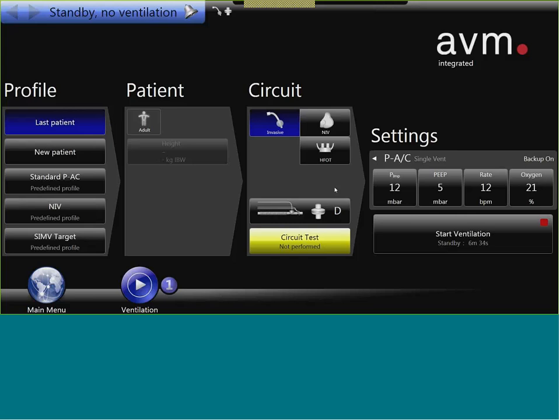So we did this on purpose. Usually you have to extubate a patient, then the patient is not ventilated at least for some seconds, and then you have to put on the mask of the patient again. And this, even when you're fast, can't be done in less than 10, 15 seconds. So there is enough time to switch the ventilator from invasive to non-invasive.